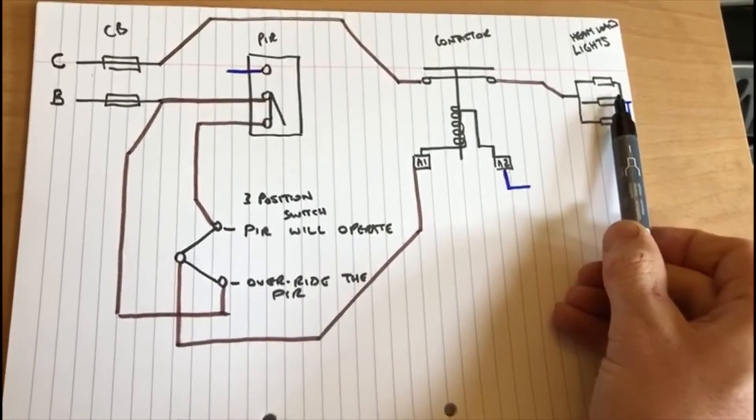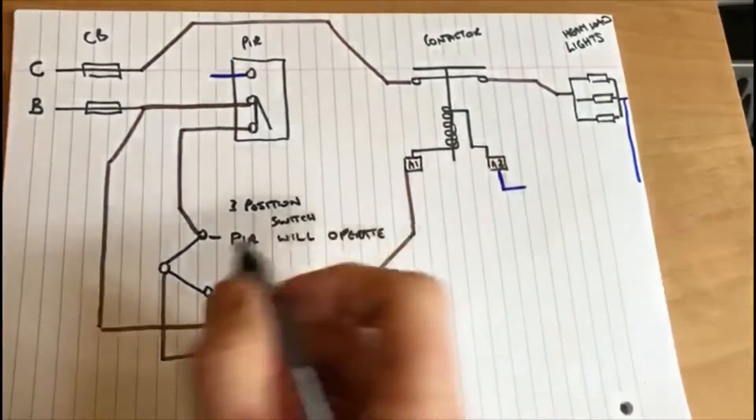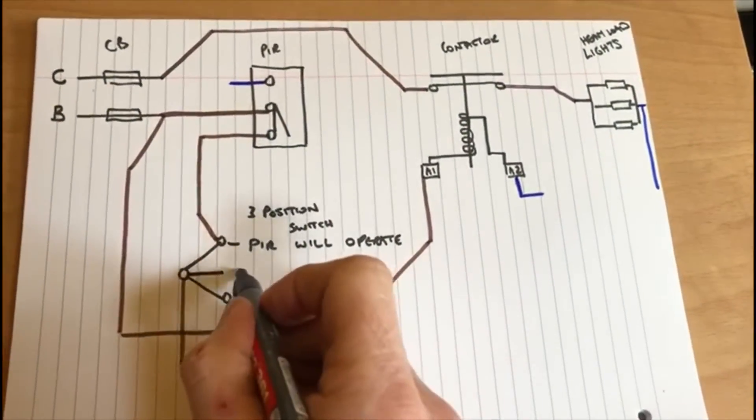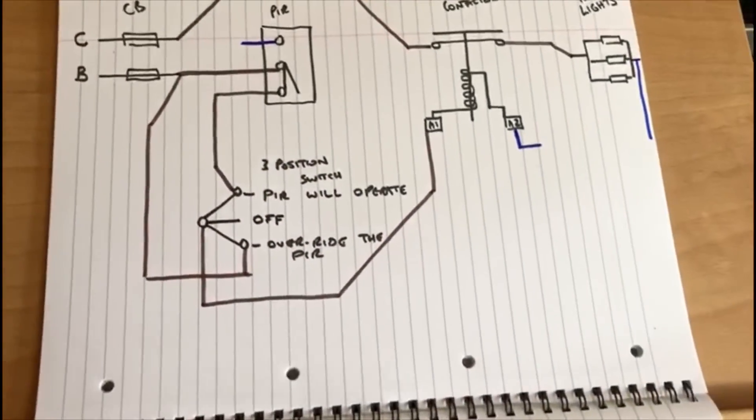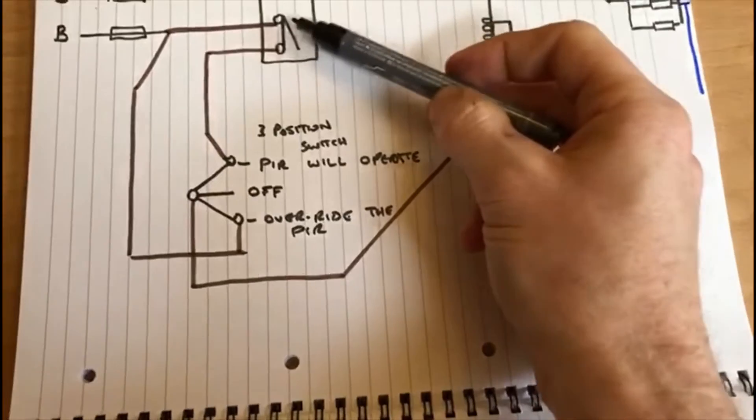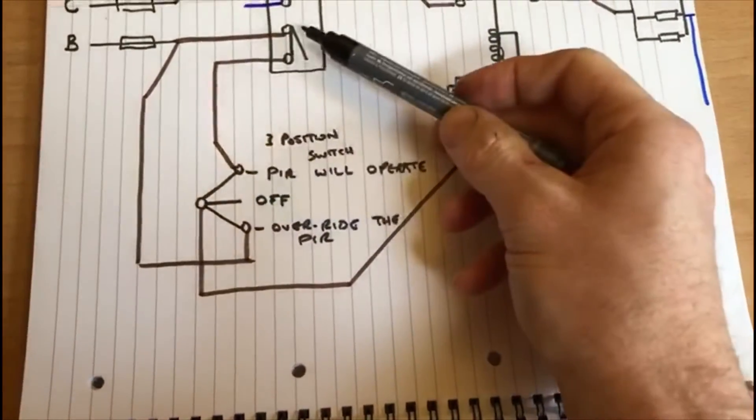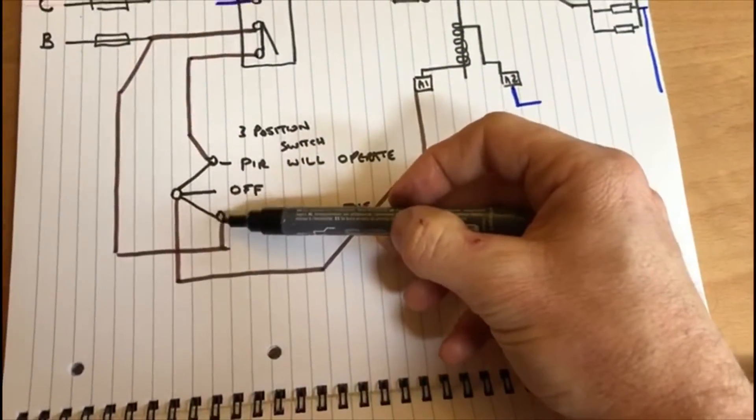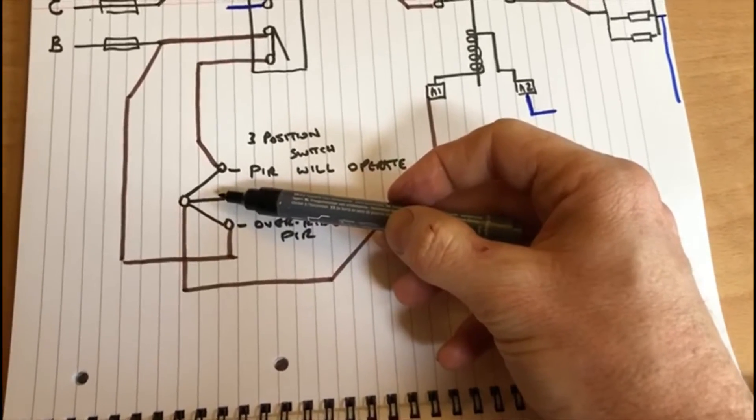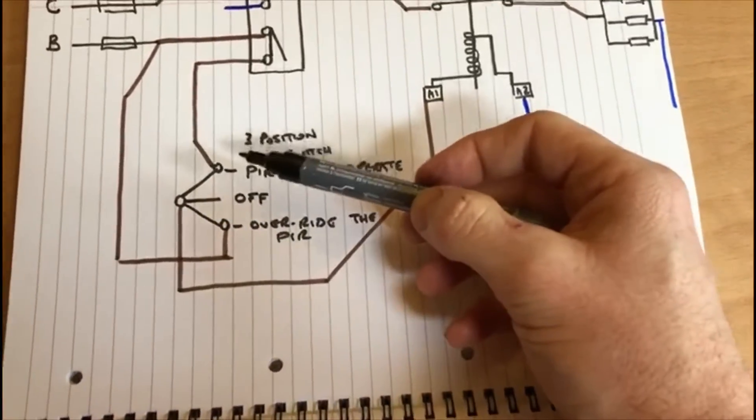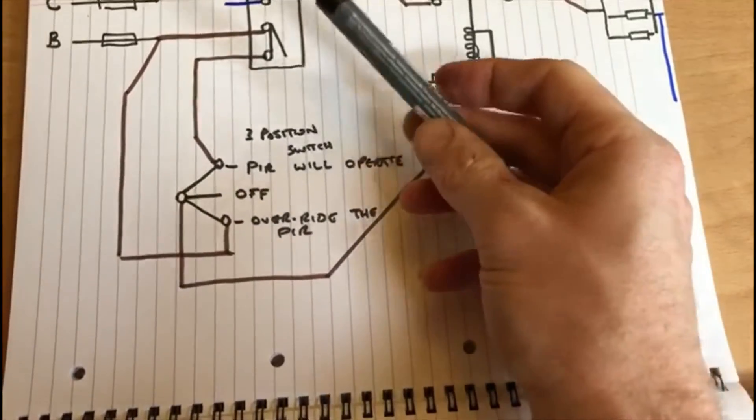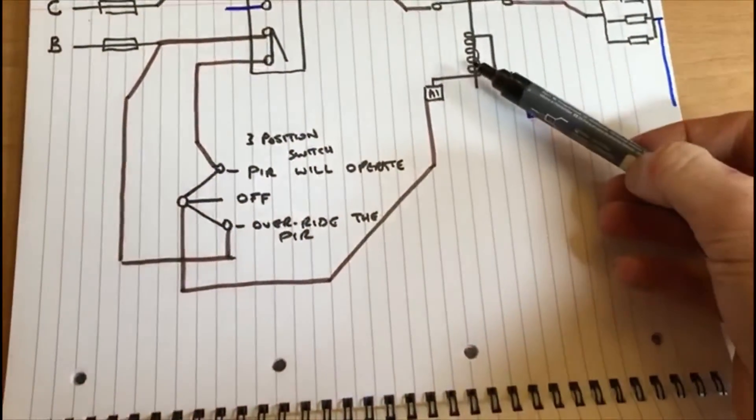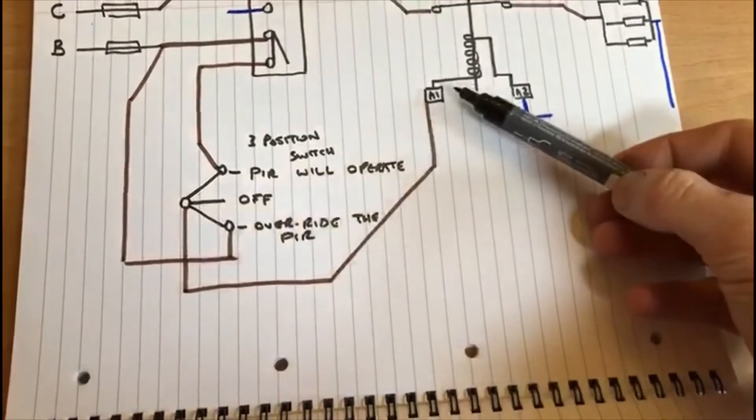Finally we have our off position and in this case the PIR will still operate but there is no connection and there is no live feed going on there. So in this position, in the off position, the PIR will not operate the coil and neither will the coil operate because there's no live feed going to it.